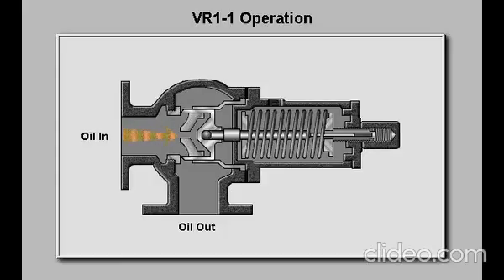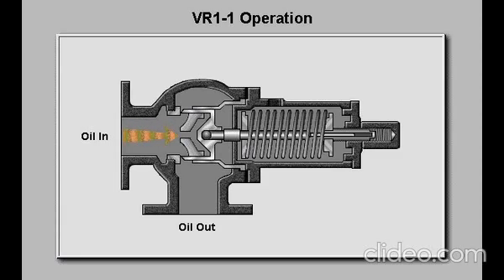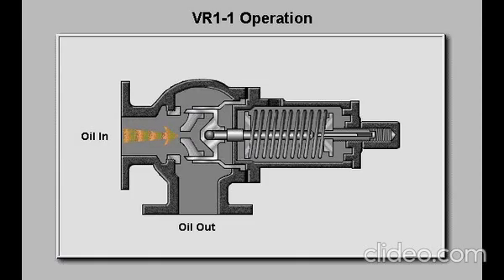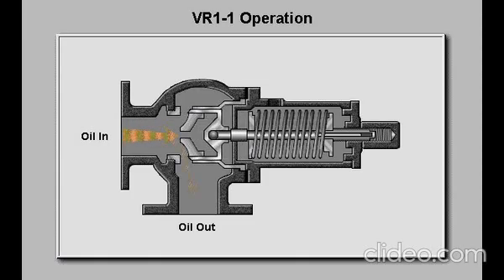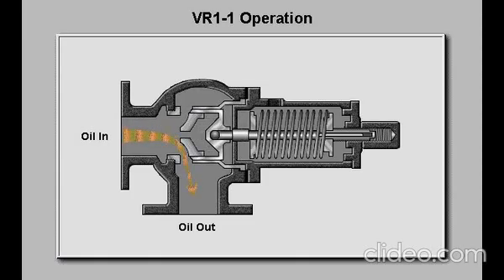If lube oil pressure in the pump discharge header exceeds 101 PSI, the cup disc in the body of the relief valve will be forced in the direction of the spring, overcoming the spring tension, and lube oil will flow through the cutouts in the seat bushing and return to the lube oil tank.